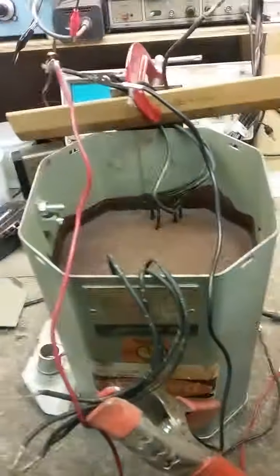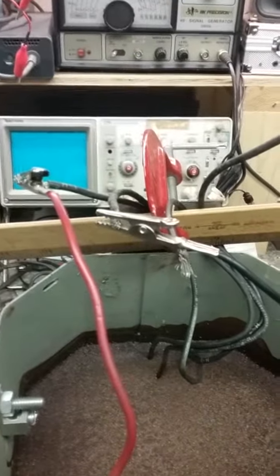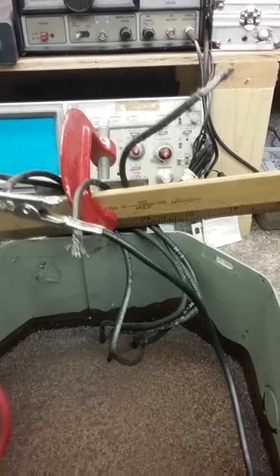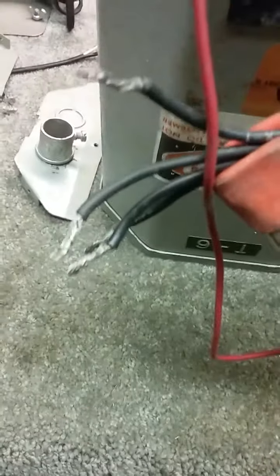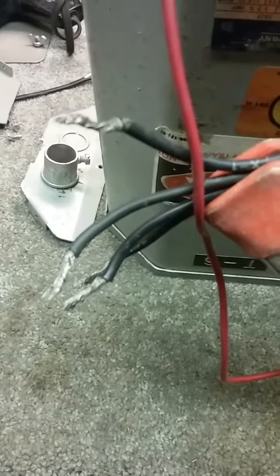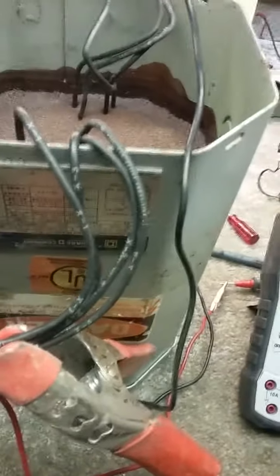Okay, I'm back. I've got my cables connected here. I have 2 alligator cables connected to the first coil of the primary, and we're showing 2.8 ohms. And I had to switch the wires around a little bit here. I kind of told you wrong. The primary coil is H1 and H2, and the second primary coil is H3, H4, which are the ones with no lead, no connectors on them. And I had to switch these around too. They also go X1, X2, secondary first coil, X3, X4, secondary second coil. They show them crossed on the diagram back there, but that's just how you tie them together to get different voltage drops.